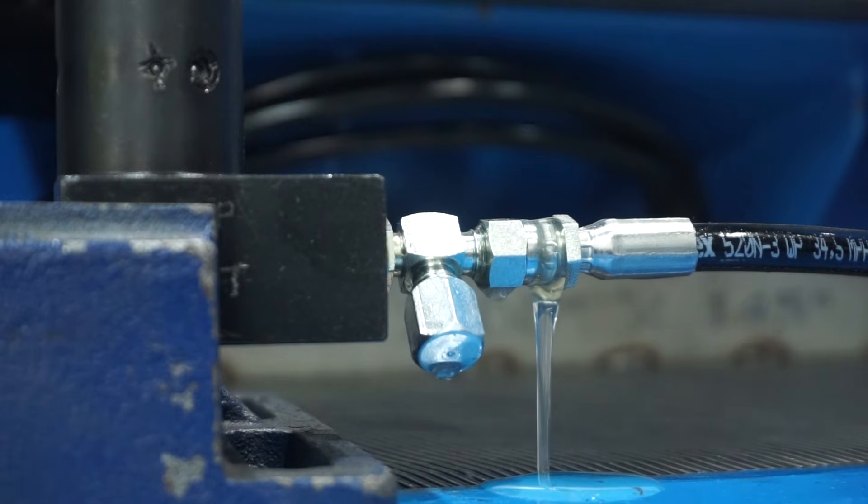Oil with air in it will appear milky from the small bubbles in it. Allow the oil to flow until it is clear, then tighten the fitting.